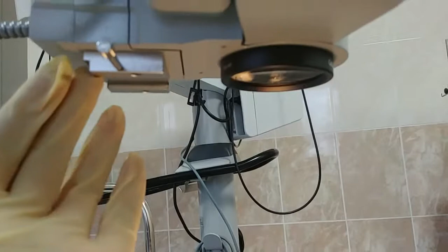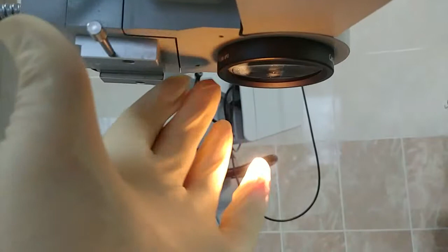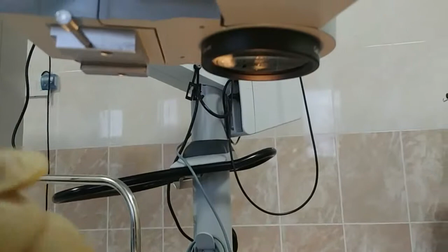First, you have to have the dovetail adapter, the standard adapter for the microscope. And secondly, the objective on the microscope needs to be 200 millimeters working distance or longer. The 175 millimeter working distance is too short because Polaris will take up some of the surgical space. So this objective can be easily unscrewed and replaced with another objective that has 200 millimeters or longer working distance. The working distance is marked on the objective in millimeters.